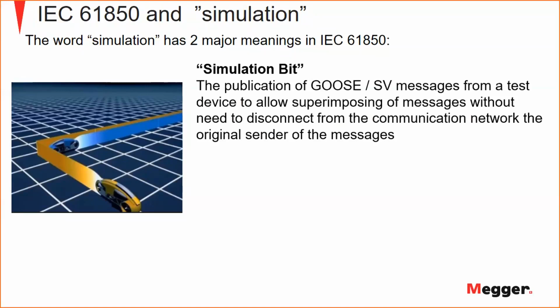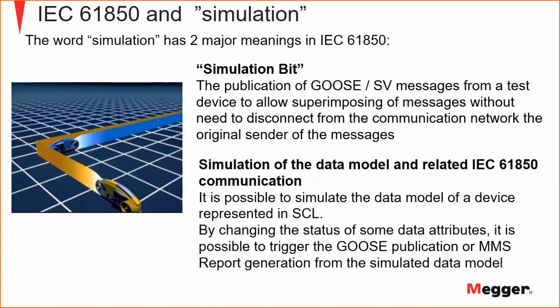We have a sort of simulation bit in our GOOSE messages or in our sample values messages. You raise this bit, I make it simplified, and you tell the network, this is not a real message, this is a test, this is a message from a test equipment. It is intended to be used for some tests. This allows us to discriminate real messages from simulated messages, and without that we need to disconnect some equipment from the network for testing. It looks strange, but it's a very good idea, and it works very well if used by everybody.